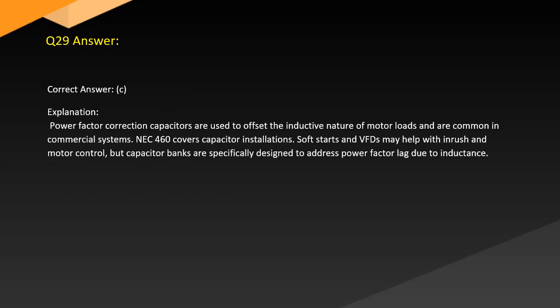Answer. Correct answer. C. Explanation. Power factor correction capacitors are used to offset the inductive nature of motor loads and are common in commercial systems. NEC 460 covers capacitor installations. Soft starts and VFDs may help with inrush and motor control, but capacitor banks are specifically designed to address power factor lag due to inductance.